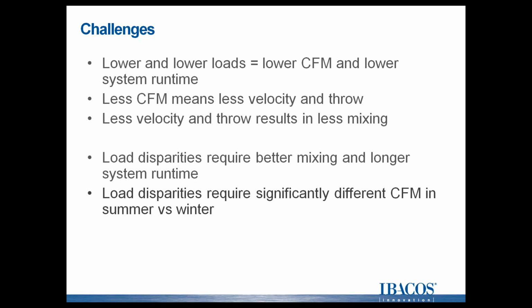And something that we're finding more and more provides a good alternative is to look at these higher velocity systems and design your system to maintain something like 600 feet per minute out of the register in order to adequately mix that room, to get adequate throw. And along that line, it's also necessary to think about the register, to think about the outlet, and pick one which will provide adequate throw and mixing. You can't just use one register for the entire house, whatever is available. You really have to select that and change that depending on your CFM.